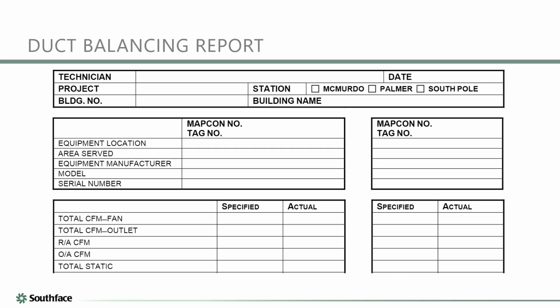And when we say, on that first slide, "to industry standards," Hugh, would you generally agree that people are looking at a 10% type of range? What would you consider an industry standard to say, yes, the system is successfully balanced correctly? 10% can be large, right? Because if you're doing 10% per grill, that could add up quite quickly. So I would say the closer you get to your design number, the better you're going to be. Okay.